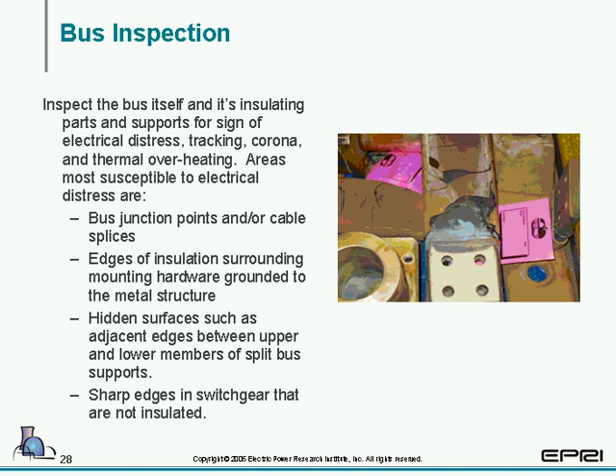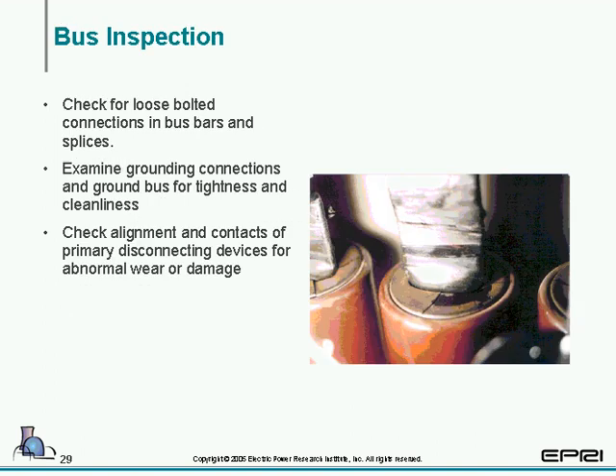The next we'll take a look at is inspection of the bus itself. You look at the bus joints, the edges of the insulation, again hidden surfaces, adjacent edges, sharp edges, and we have more on the next slide. We're going to check for loose bolts, examine grounding connections, and check alignments.